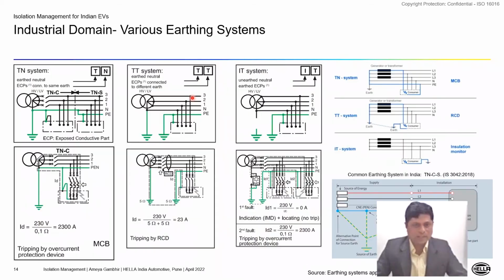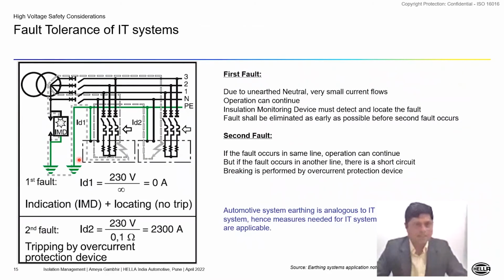So just one step back, in a TN system, if there was an isolation fault, there may not be a hazard for electric shock because the short circuit is happening through wires, but then there is a power unavailability. Whereas the IT system is designed to have maximum power availability, of course, at the cost of a possible electric shock hazard, but that too, not in the first fault, but in the second fault. So in this system, if there is a compromise in isolation due to the unearthed neutral, very small current flows and the operation of the system can continue. That means there may not be an electrical shock hazard when the first fault occurs in an IT system.